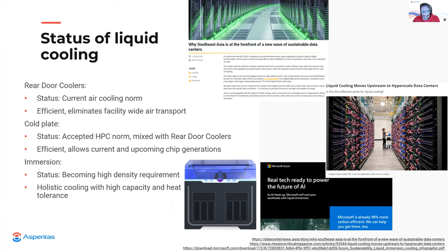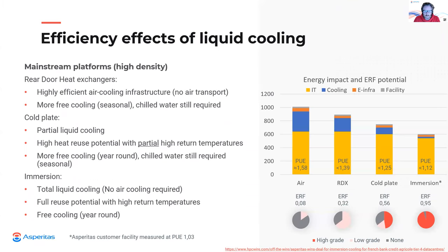Immersion is also known from HPC applications and is now breaking through to become a mainstream strategy for HPC and high density platforms. The biggest value of immersion lies in the holistic cooling approach. Since the IT equipment is fully immersed, 100% of the converted energy is captured in the dielectric liquid. And this holistic cooling ability is therefore the most important contributor to addressing efficiency and sustainability goals.